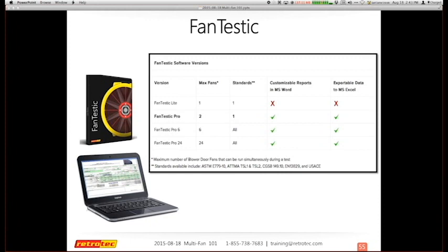It is designed to tell you which way you're testing and that you're covering your fans, and it does the exact number of multi-point tests for your baseline and your test itself, and then your baseline again, and then says, okay, here are your results. So you're not trying to just log some data and then decide what to use, or wonder whether you took enough points. It just does the test for you and does give you some flexibility.